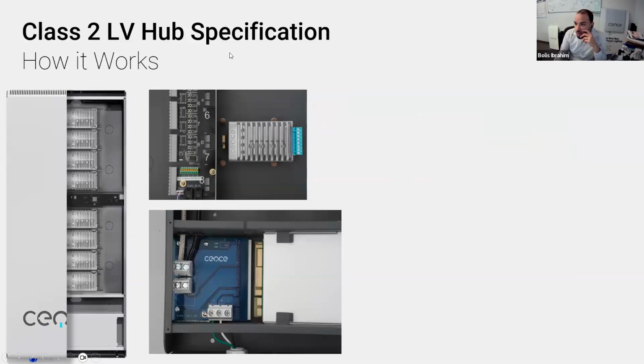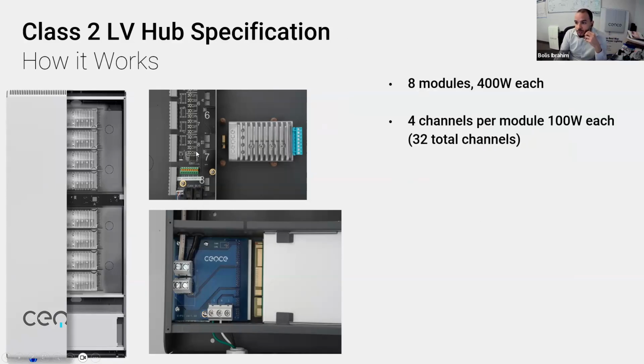Typically, when you look at a class 2 low voltage system, the specs you'll be looking at are: what is the input voltage, what are the output voltages, how much power can it handle, and what control interfaces are there. Our system, for example, is modular, so 8 modules, 400 watts each. There's 32 circuits, because class 2 low voltage circuits are capped at 100 VA or 100 watts per code, and 60 volts maximum, 100 watts maximum. So that's something you'll look for as well, what are the voltage ranges, and the power is going to be capped at 100 watts. You want to make sure the outputs can go up to 100 watts. A lot of stuff on the market is going to be 96, 90, and that's one of the things that happened with PoE, is it couldn't source 100 watts at the output end.